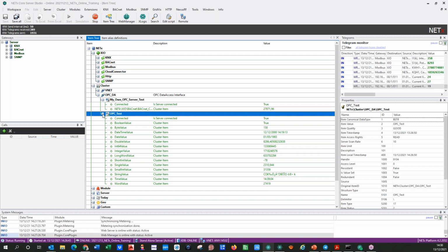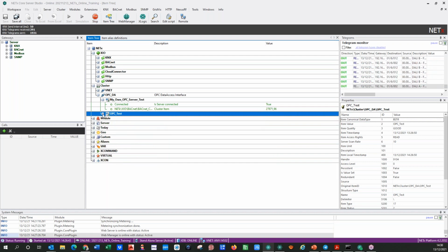So how we could read information from an OPC. I mentioned before that OPC servers are useful in some cases to give the BMS some information, for example, coming from fire alarm systems, or old automation systems. In some cases, the OPC is the only way that we can get all this information. For example, for LonWorks systems is also a typical situation.